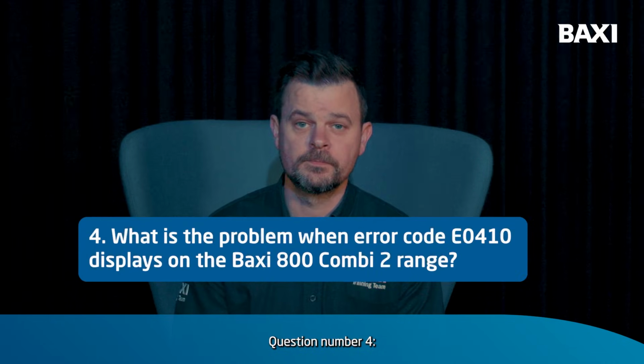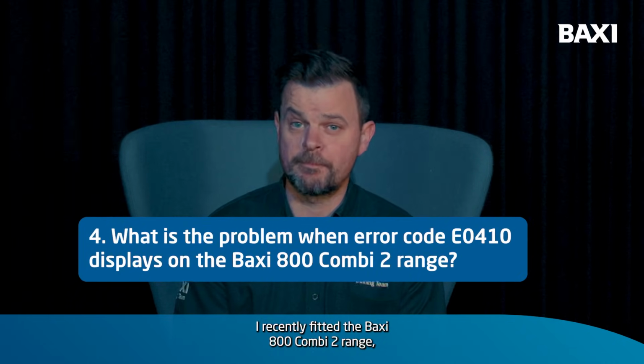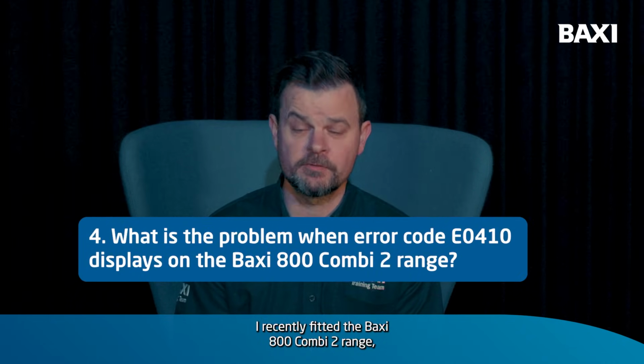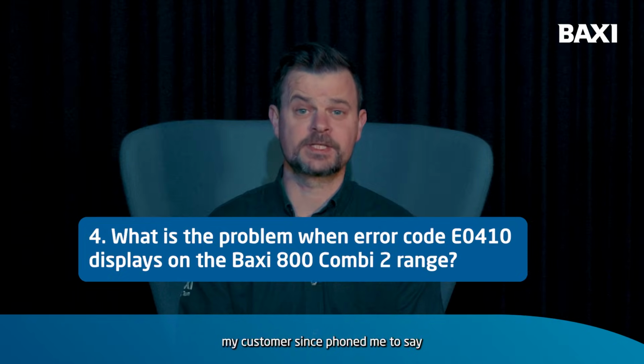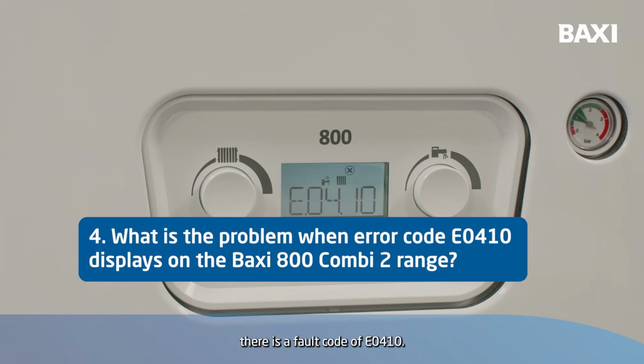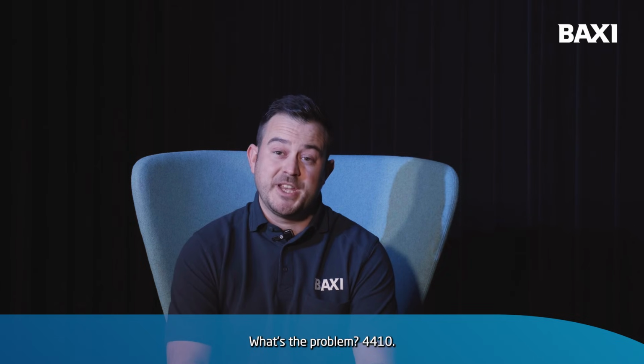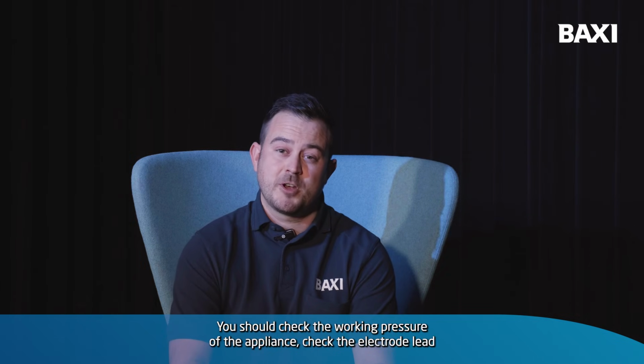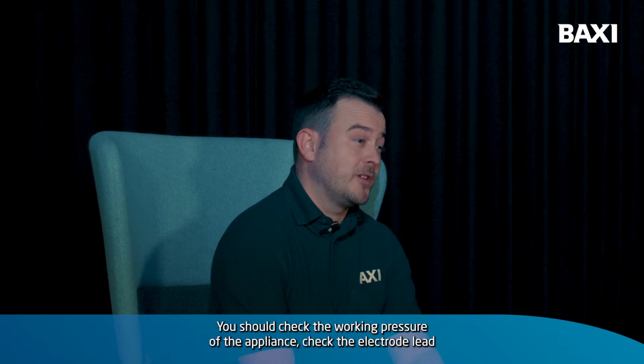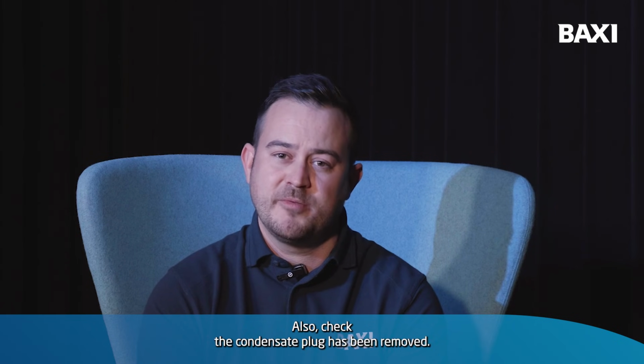Question number 4. I recently fitted the Baxi 800 Combi 2 range. My customer has since phoned me to say there is a fault code of E0410. What's the problem? For E410, you should check the working pressure of the appliance. Check the electrode lead and all earth leads are fully pushed onto the PCB and electrode. Also check the condensate bung has been removed.